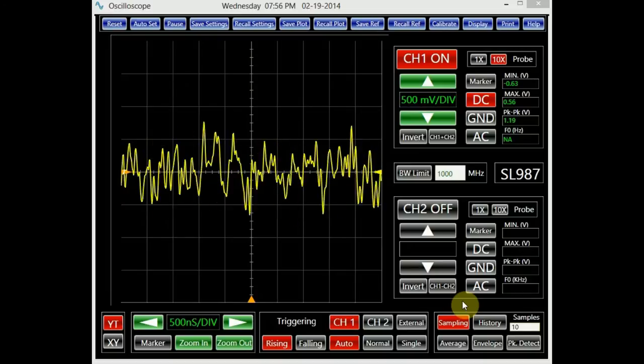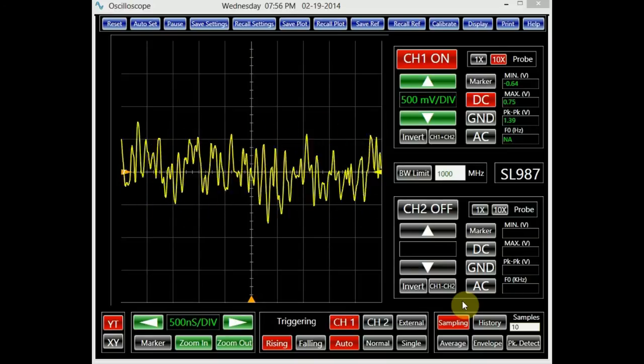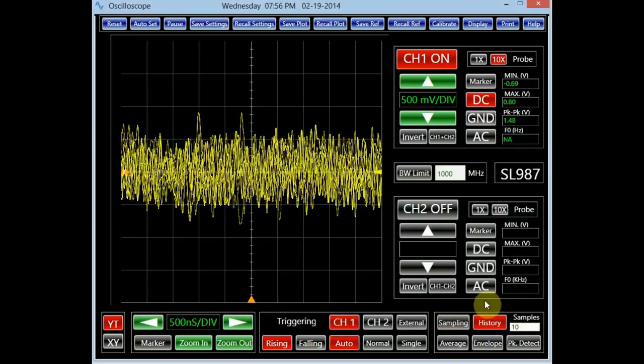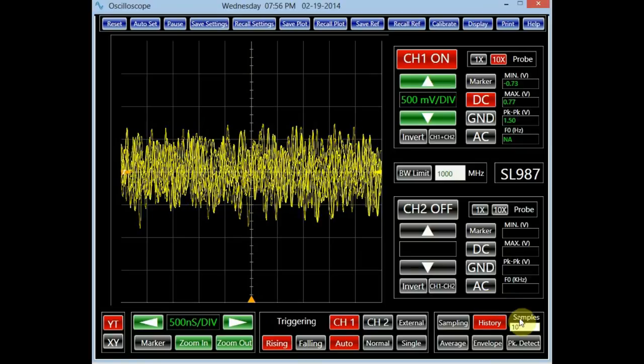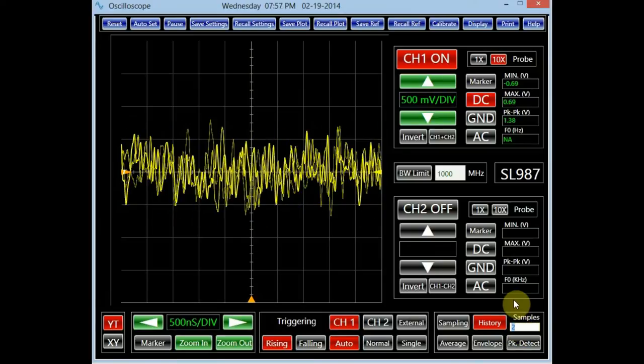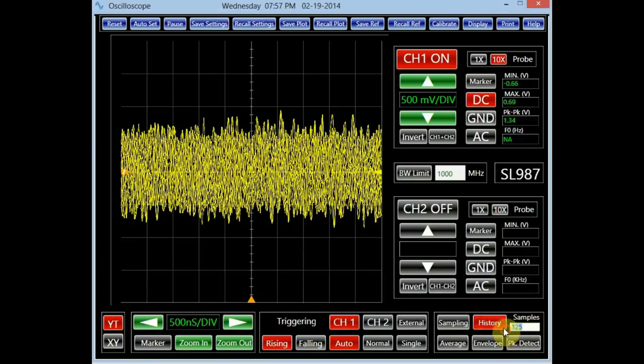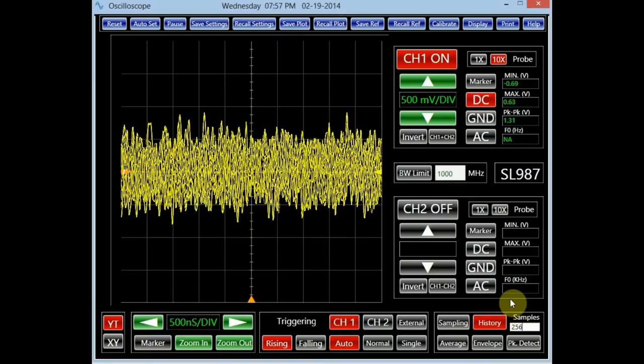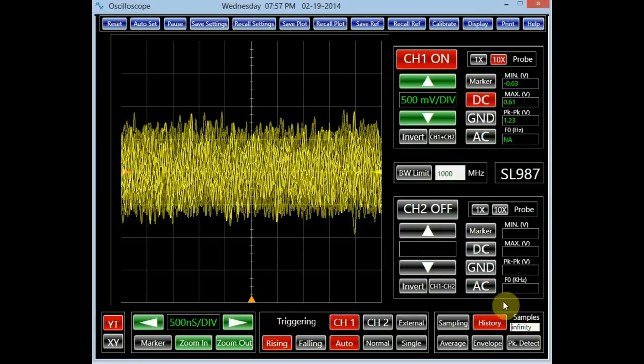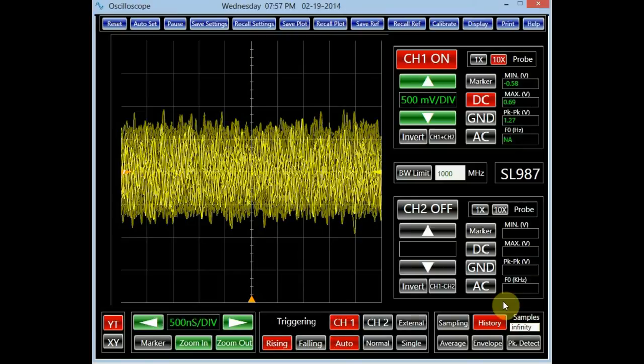Also, each time the screen is updated, the previous data is erased from the screen. In the history mode, however, the screen retains the data. The number of retained acquired data sets can be changed by entering the desired value in the sample text box, ranging from 1 to 256. To maintain all the previous data, simply input an 'I' in the sample text box. Notice the older data are displayed with a lesser intensity. History tracks signal changes and displays a collective set of data. It is the method of choice for observing signal variation over time.